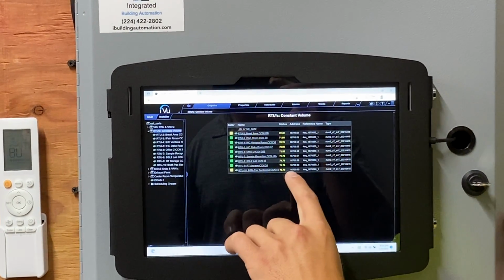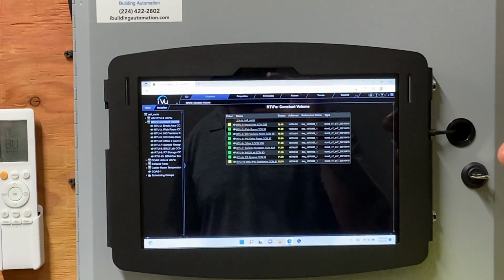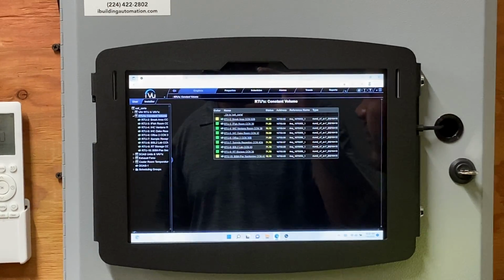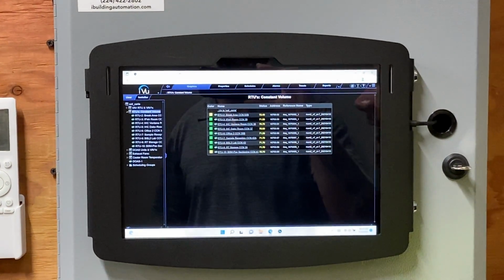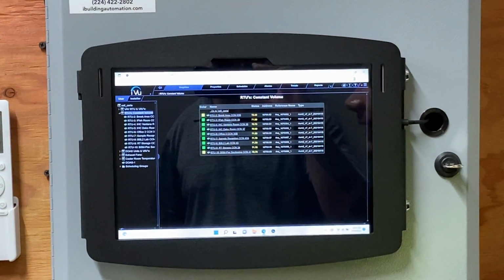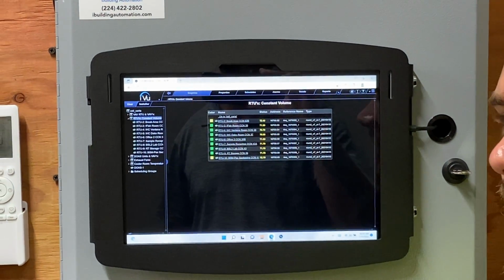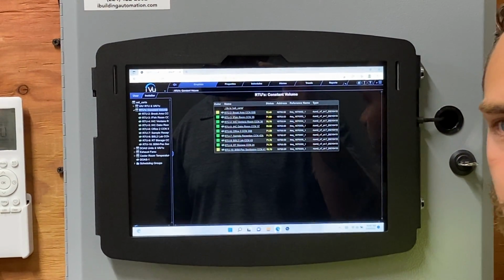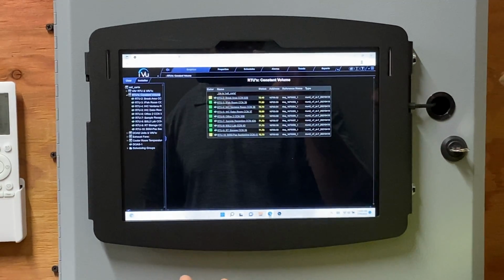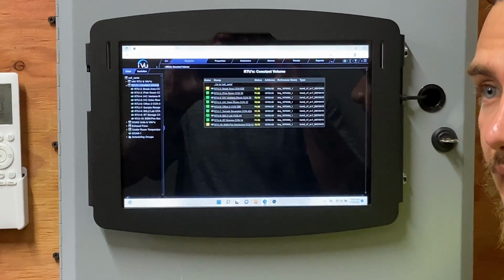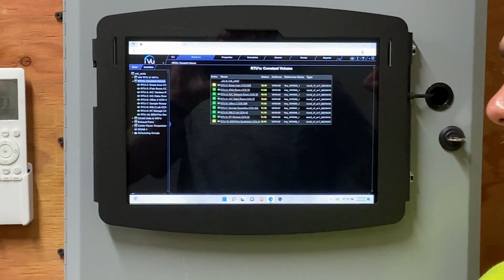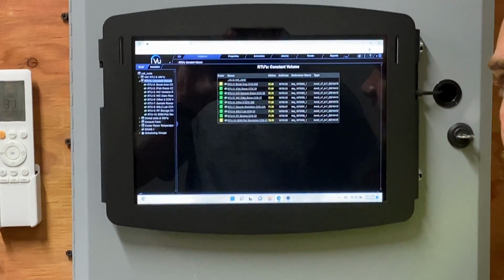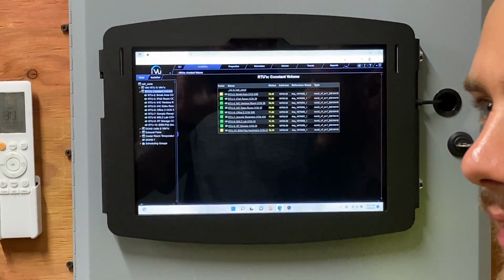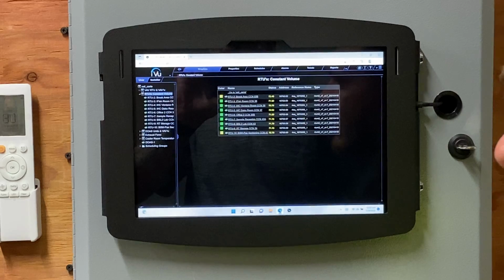It's yellow now because of that 0.70, we're just over the cuff of 72 degrees, so it's kind of saying, hey, we're a little warm in here. But the equipment isn't smart enough to work off decimal values, the control just gives it to you, the sensor makes it happen. I'm not going to base something off half a degree, so you basically use whole degrees, and the equipment will work better that way.